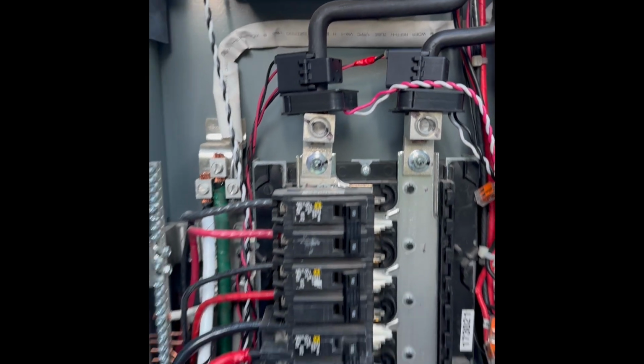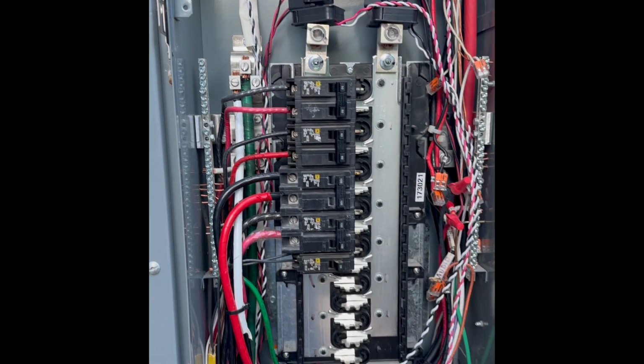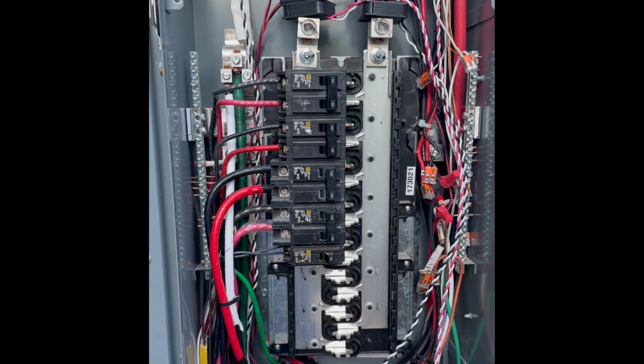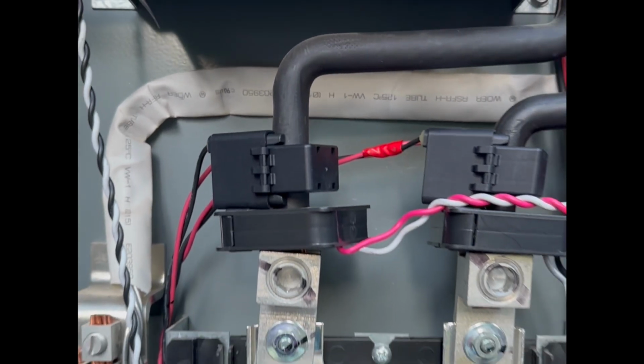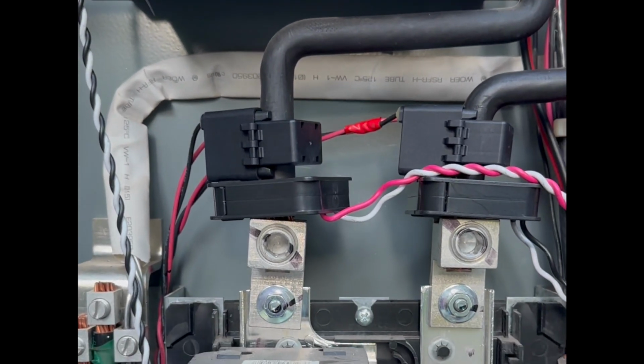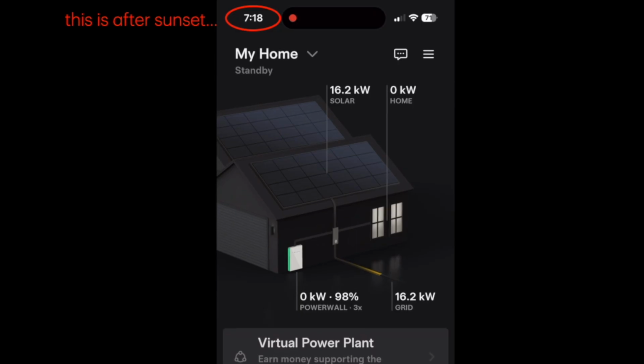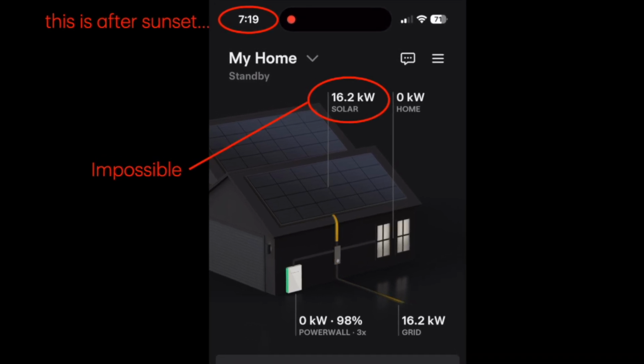Does it matter? In this case, yes, because unlike solar production, which is perfectly balanced between the red and black wires, these breaker panels won't have perfectly balanced loads on the two phases. There could be an appliance on the black phase that uses a lot more current than on the red phase. So these CTs need to be on the correct phase, with the label facing the source. So the installer hadn't installed CT1 and CT2 upside down, but rather on the wrong phase, and I can't really blame them because it's pretty odd to have the red phase on the left side of the panel. I can blame them for not testing their metering though.